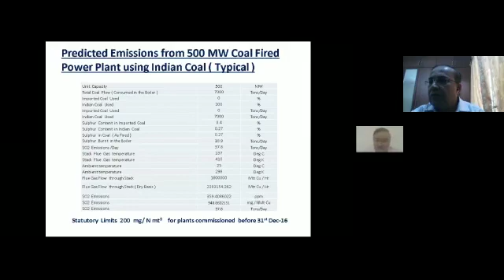And I just wanted to throw some light on where exactly the measurement of sulfur dioxide and NOx is taken. Generally, people will say, okay, I will take it on ID fan discharge and all that. It's not allowed. It doesn't give any representative reading. These are the measurements as prescribed by the pollution board.